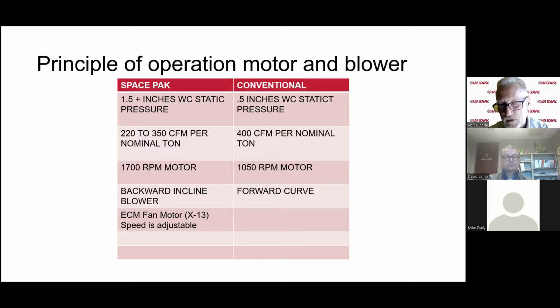Conventional system, as we all know, 400 CFM per nominal ton. We've got a 1700 RPM motor on the SpacePak system. We've got a 1050 RPM motor. All right, so we have more rotations, and you'll see as we go through here, we have a 10x6 wheel, but it's a backwards inclined wheel, and it can handle the high static that we are looking to achieve in our ductwork.